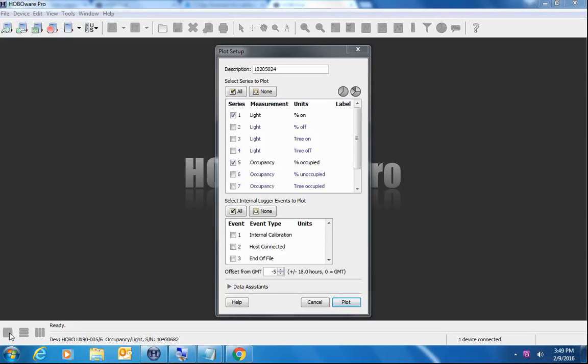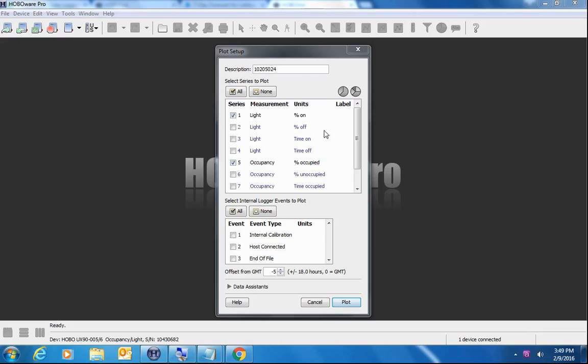We've also offloaded some data from a UX 90 005 that was recording light on off and occupancy data in runtime mode. So that's what we're seeing here in the plot setup screen. By default, HoboWare is enabling the percentage of time on during each interval for the light sensor and the occupancy sensor, the percent of time on and percent of time occupied during the logging interval. This particular interval was set to 10 minutes.